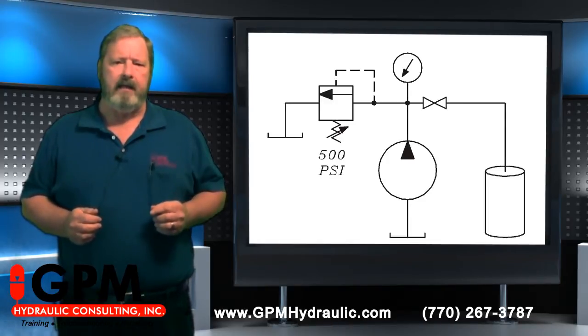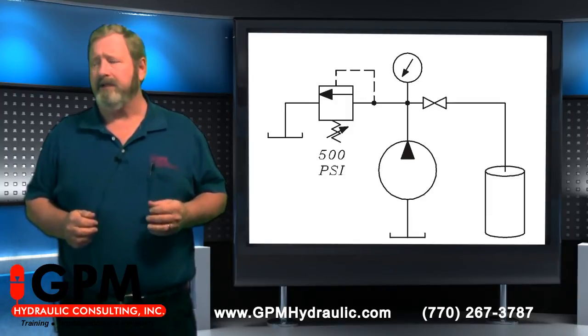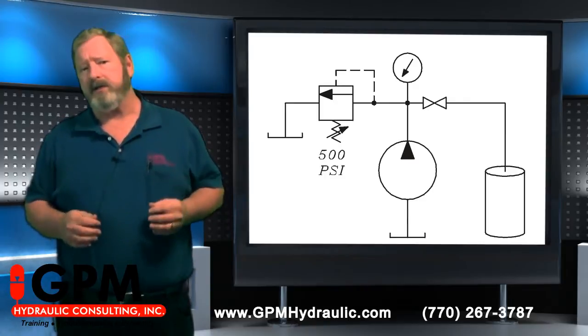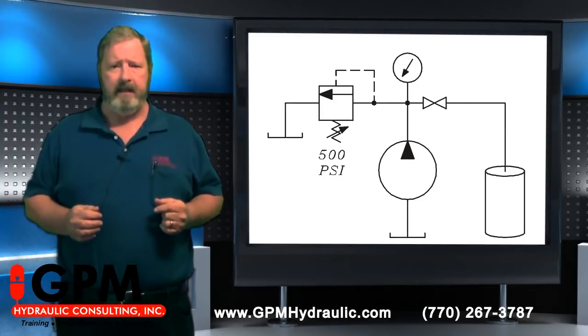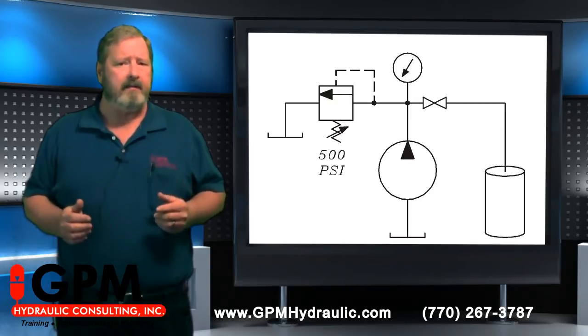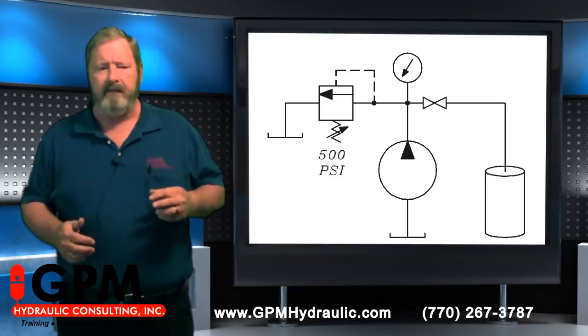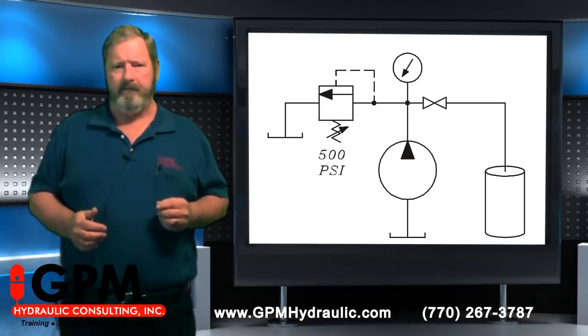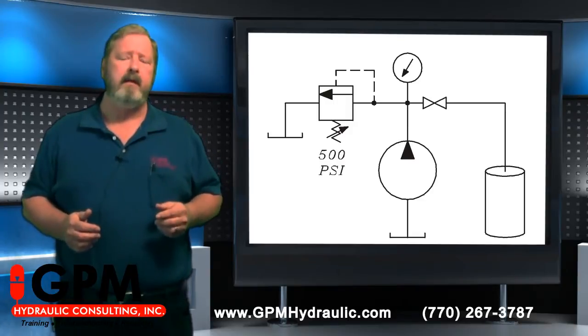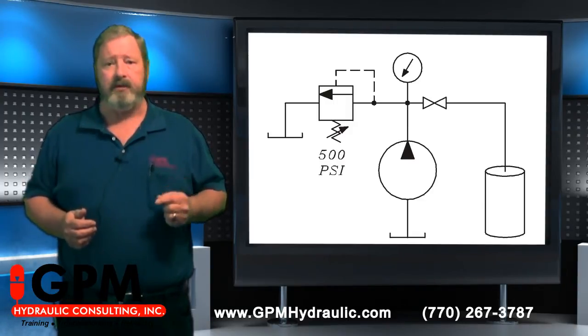Most people think that the pump pumps the pressure — in other words, that's where the pressure comes from. And if the system pressure is lower than it should be, the problem is probably the pump. This is not true. The pump doesn't pump pressure; it delivers a rate of flow. That flow meets with, and hopefully overcomes, a resistance, and the result of this is pressure.